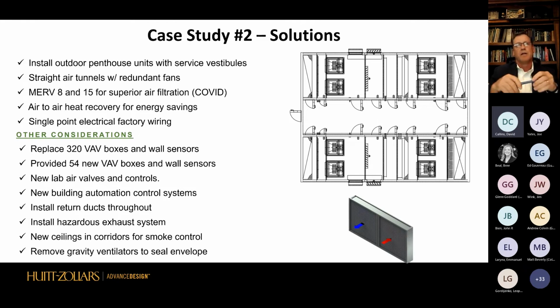At this point, the CUP, the central plant, was designed by another firm, like for like. That firm did exactly what they were supposed to do - what the client told them to do - go out there, categorize, get all the pumps and everything. Now that we know the engineering of the building, we have to marry it up to the plant, and really, everything was oversized. So we said, okay, right size it.